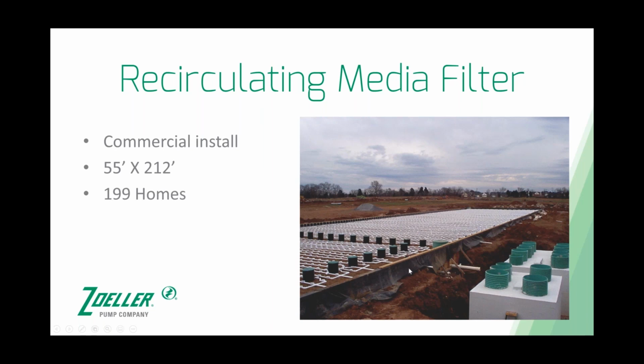And then underneath of that, usually on these larger systems, we use leaching chambers for our collection network piping underneath. This is an underdrain system. And again, when this doses out, 80% of that is going to return back into the pump tank and be redosed again throughout the day. 20% is going to go to final dispersal. This will get about 6 inches of gravel over top of the piping. You won't see that. These are cleanouts that go down into the leaching chambers on the ends of the leaching chambers, where we can clean those solids out if ever need be with a septic tank pumper truck.